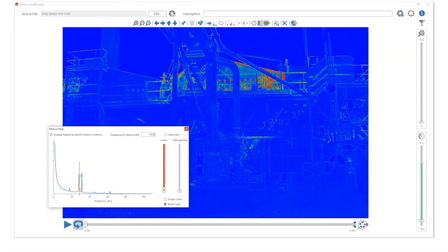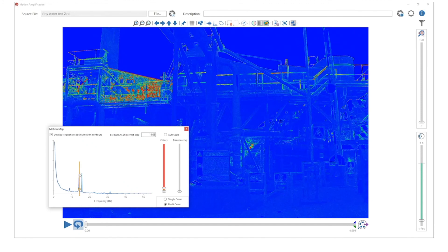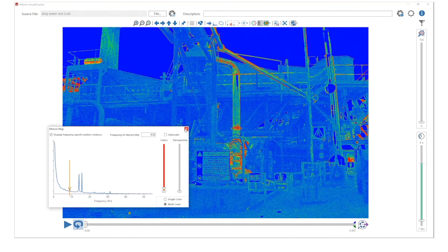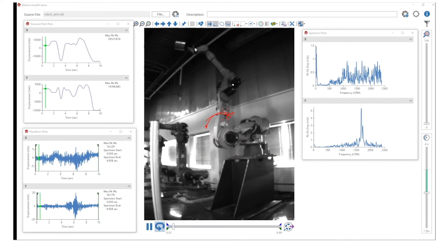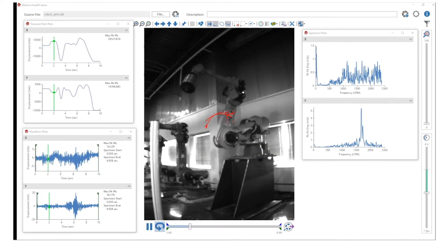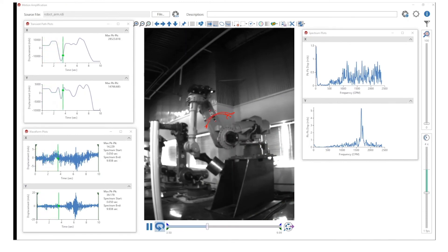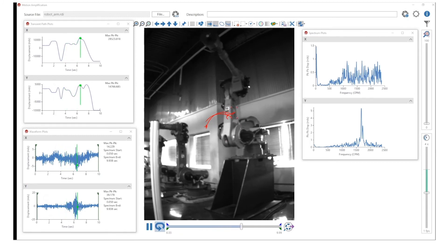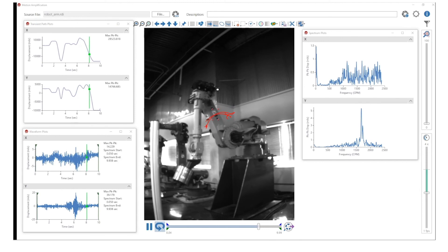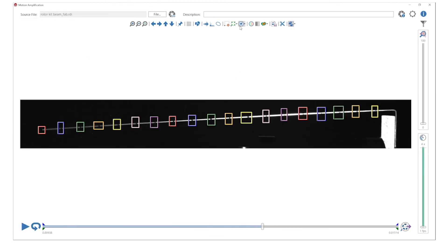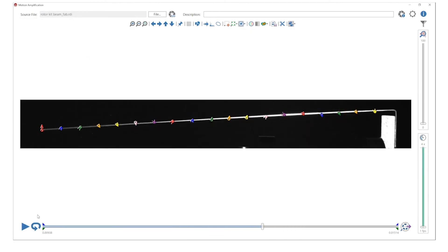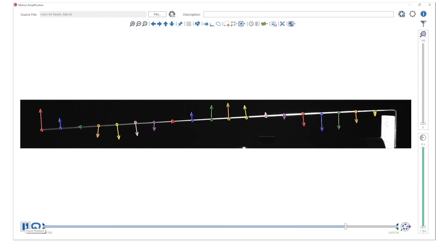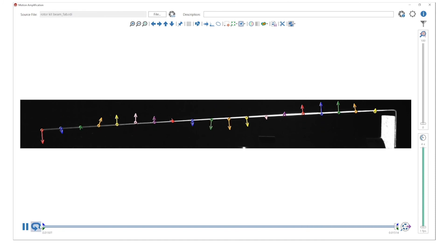Motion maps, which are colorized overlays of motion at a specific frequency, give you yet another way to visualize motion. Transient regions of interest allow you to track motion within the image, measure and plot that motion, and separate the transient and dynamic motion as the object moves through the scene. Also included is the use of vectors to visualize direction and magnitude. You can easily show mode shapes, nodes, and antinodes and visualize phase.